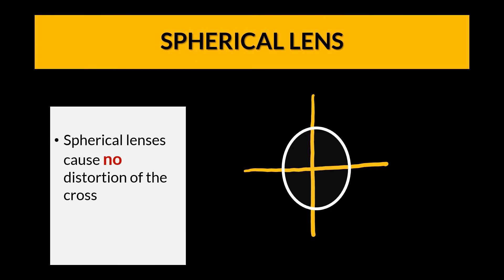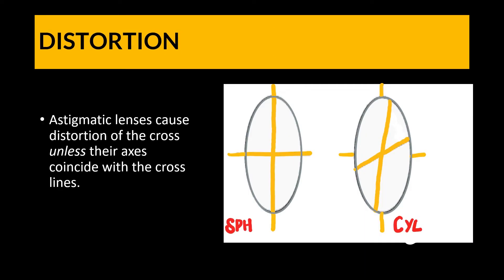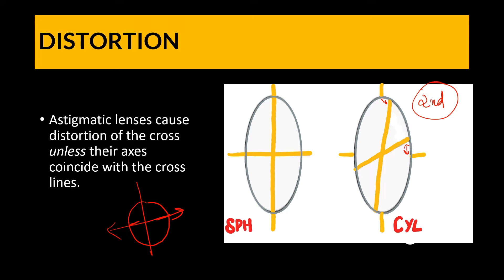A spherical lens has equal power in all meridians, so when you look at a cross through a spherical lens, there will be no distortion. If you see any distortion of the cross after placing the lens — where the cross appears broken — that is called distortion and it happens with astigmatic lenses. However, if the axis of the cylindrical lens is aligned with the cross, you will not see any distortion, so that is an important point to remember.